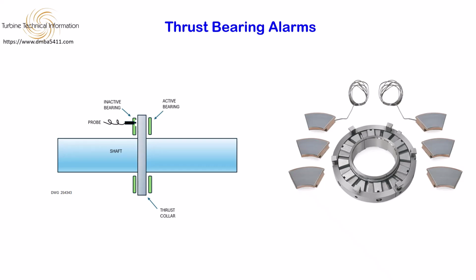How thrust position is monitored. Monitoring is typically achieved through a combination of two methods. Axial thrust measurements: a transducer or probe measures the physical gap and translates it into a voltage signal. For example, a thrust channel will typically have a sensitivity of 200 mV per mil, where a mil represents a thousandth of an inch of movement. An increase in movement indicates wear on the thrust bearing.